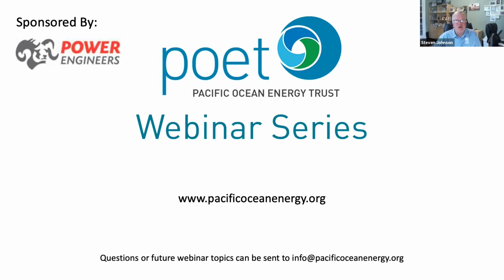Like I mentioned before, we've got to find the right location for this. We've got to look at the water depth and the materials. Once we've identified the optimum solution for the main transformer station, then we can look at how and where we run the power cables, because these power cables will certainly go down to hundreds of meters, if not 1,000 meters. So I'm not worried about the depth of the power cables, it's just making sure we can make the end terminations in the dry, and that needs a suitable platform for it.